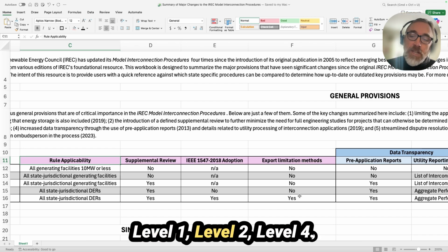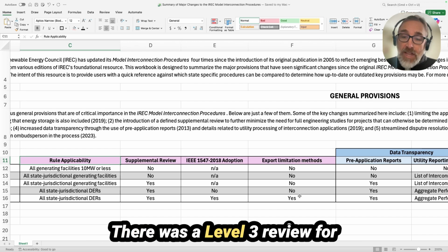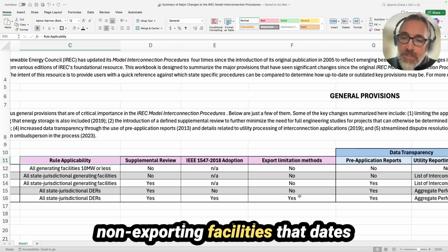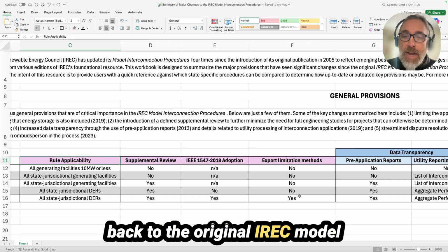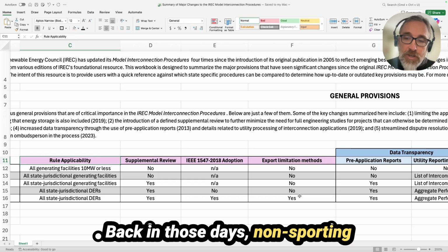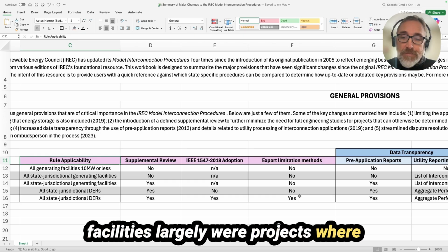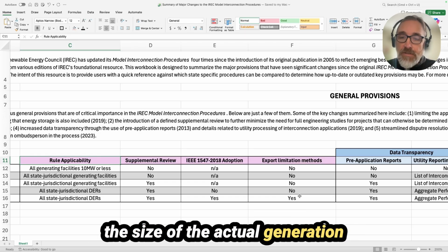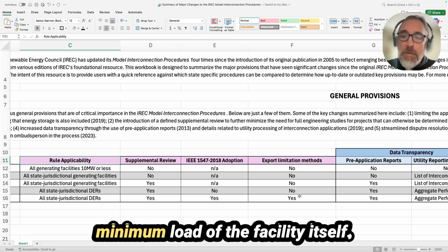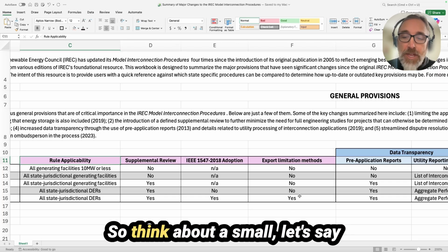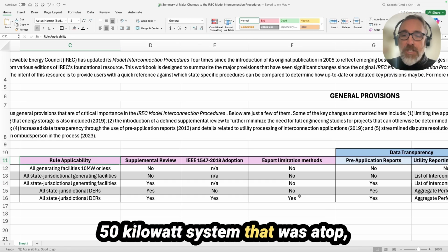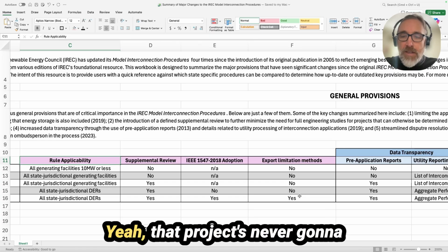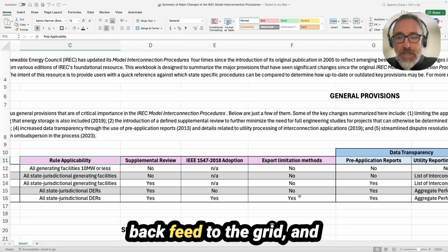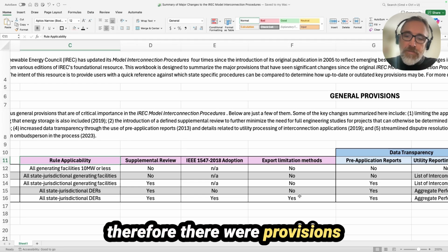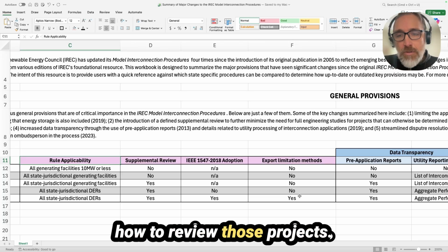You've heard me mention level 1, level 2, level 4. There was a level 3 review for non-exporting facilities that dates back to the original IREC model. Back in those days, non-exporting facilities largely were projects where the size of the actual generation facility was smaller than the minimum load of the facility itself. So think about a small, let's say 50 kilowatt system that was atop a large manufacturing plant. That project's never going to backfeed to the grid, and therefore there were provisions in there related to how to review those projects.